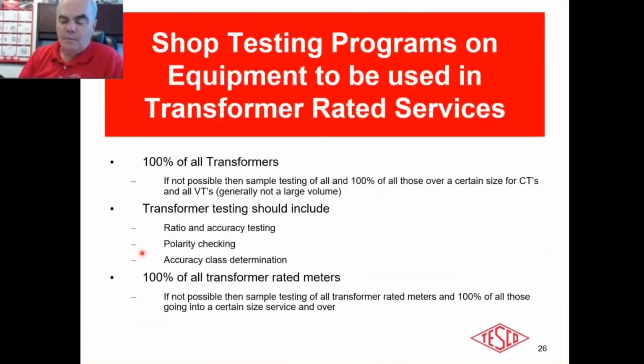So your CT should actually be as accurate as it was 30 years ago. So if you get CTs in that are 20 years old, even 25 and even 30, if they test okay, you could put them back out there. But right now there are better choices with the extended range transformers.